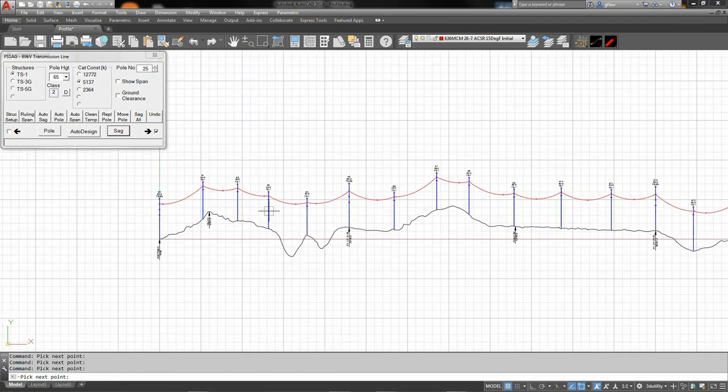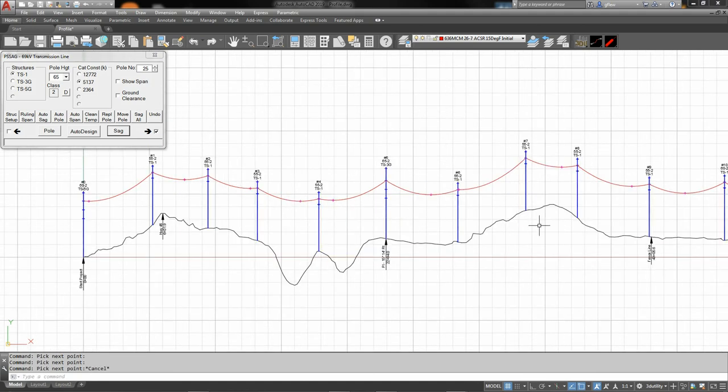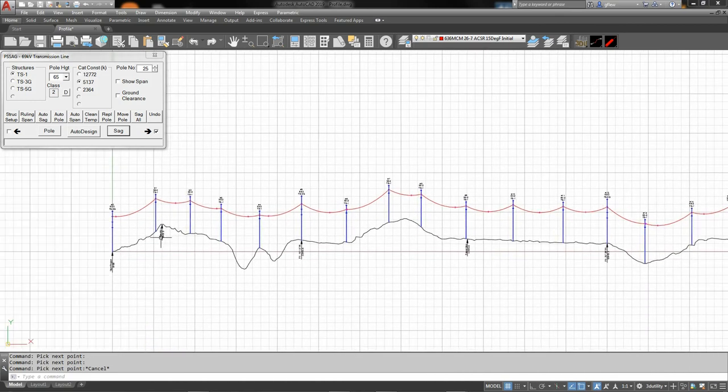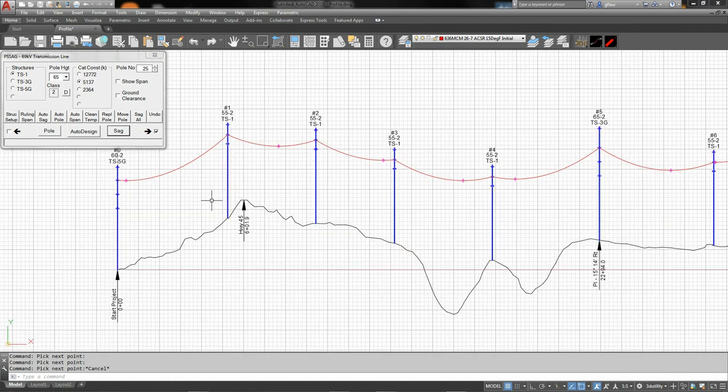Okay, so there is our initial sag, and we've gone back and made adjustments for where we found uplift problems. Now what we'd like to do is go back and put in our final sag to show that. When we select final here, you notice that our show span and ground clearance both click, which indicates we're going to show the span distance at this point, and also the ground clearance line.